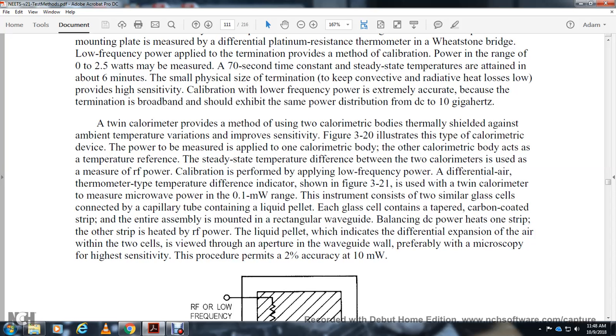Use the twin calorimeter for microwave power down to 0.1 milliwatts. The instrument consists of two similar glass cells connected to a capillary tube containing a liquid pellet. Each glass cell contains a tapered carbon-coated strip, and the entire assembly is mounted in a rectangular waveguide.